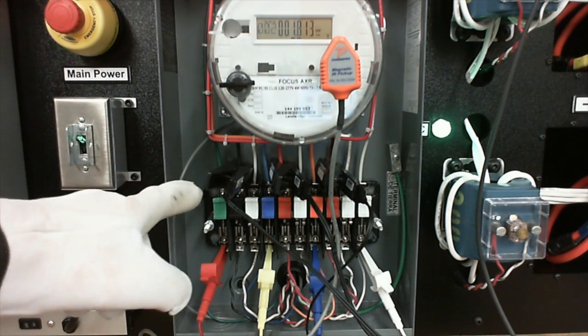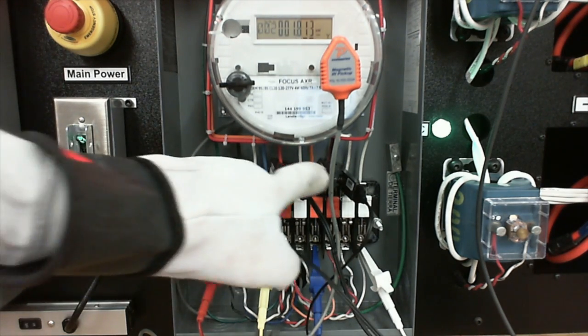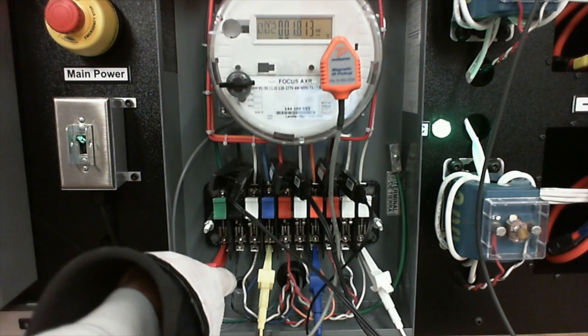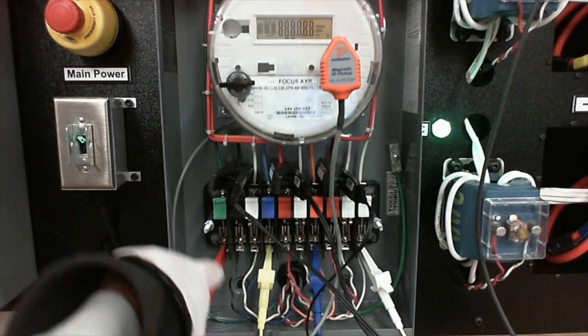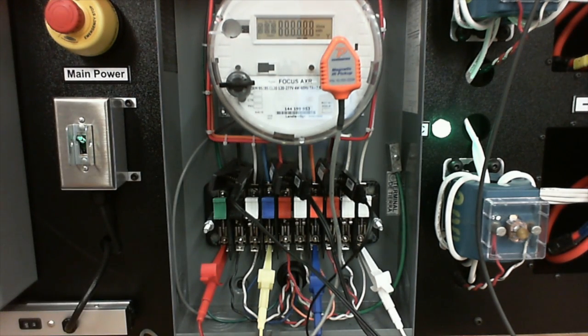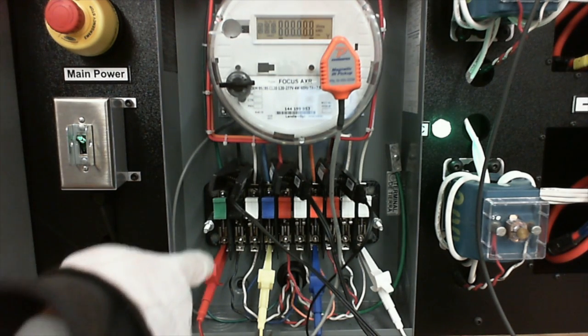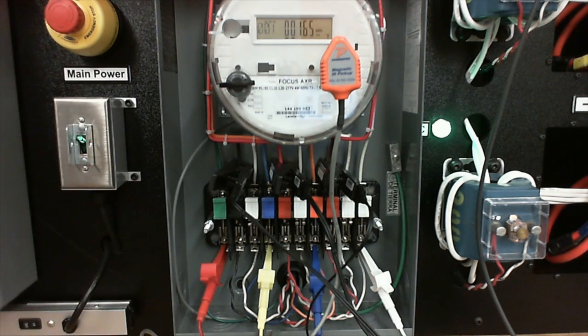So now I'm picking up my secondary current A, B, and C right here. I could come down here and get my wire coming in through the bottom of that shunt, either way. As long as I'm getting around that wire bringing my current back up to the meter, on the secondary side coming from the CTs, I'm good. I just want to get a picture of that secondary current.